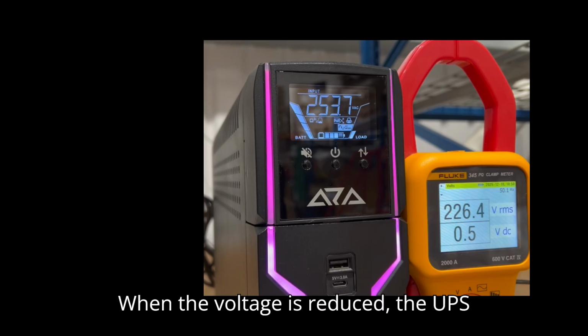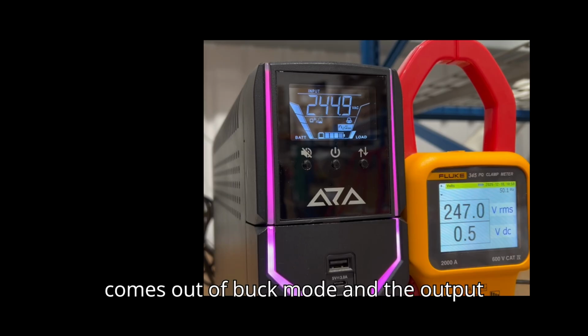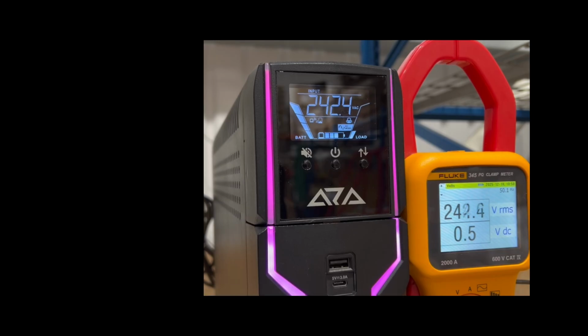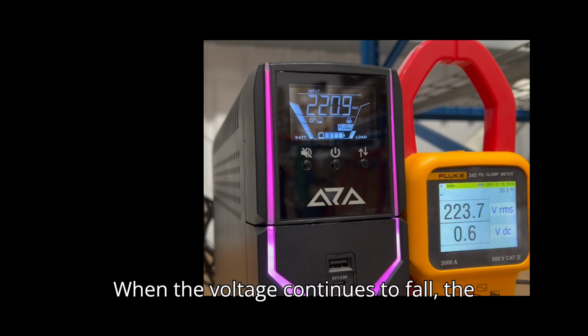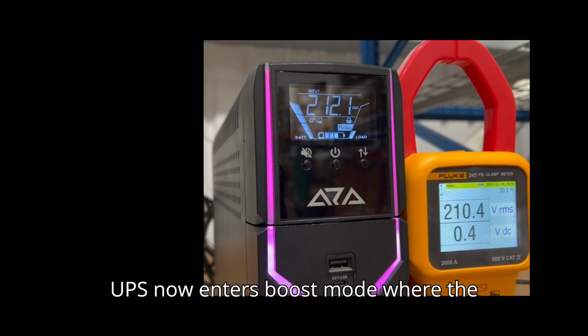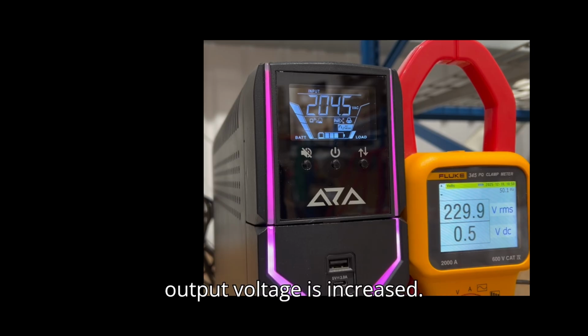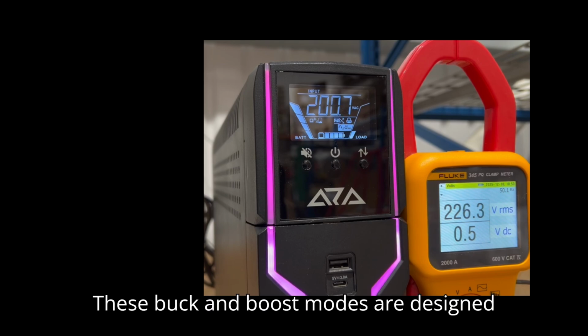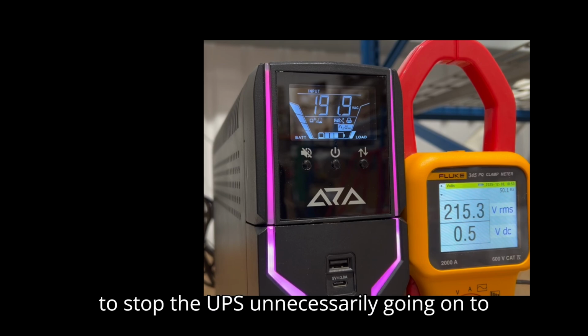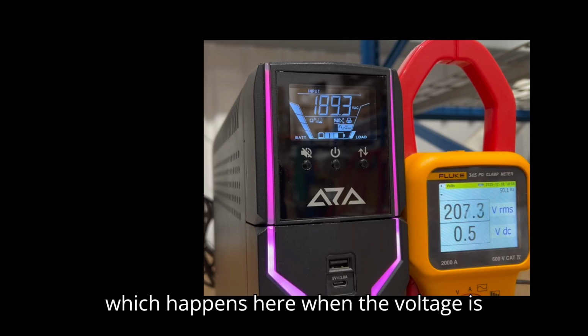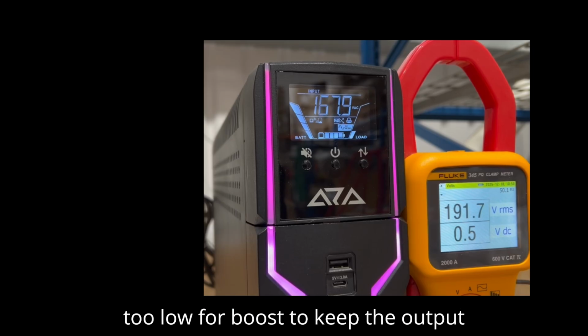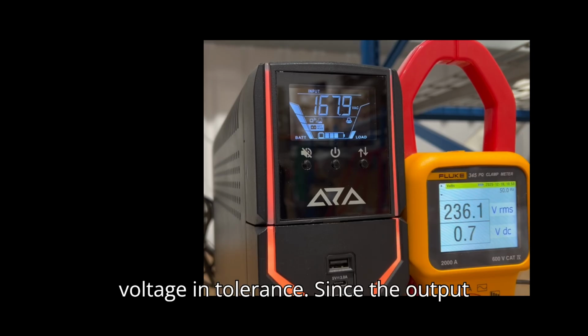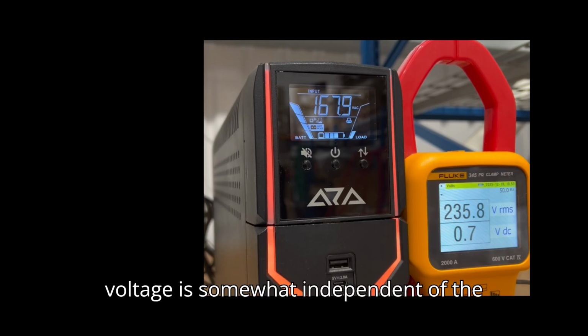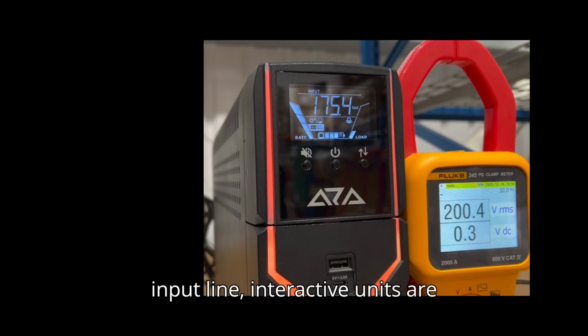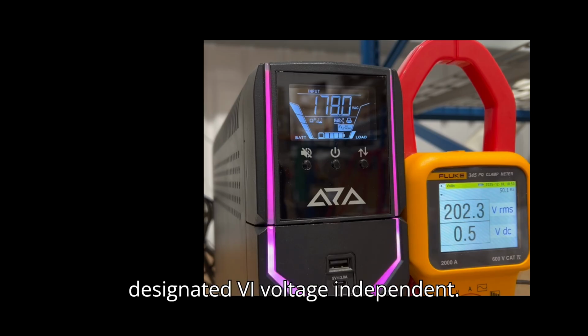When the voltage is reduced, the UPS comes out of buck mode and the output again follows the input. When the voltage continues to fall, the UPS now enters boost mode where the output voltage is increased. These buck and boost modes are designed to stop the UPS unnecessarily going onto battery power to preserve the battery, which happens here when the voltage is too low for boost to keep the output voltage in tolerance. Since the output voltage is somewhat independent of the input, line interactive units are designated VI, voltage independent.